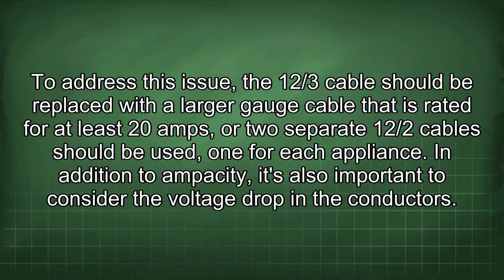To address this issue, the 12/3 cable should be replaced with a larger gauge cable that is rated for at least 20 amps, or two separate 12/2 cables should be used, one for each appliance. In addition to ampacity, it's also important to consider the voltage drop in the conductors.